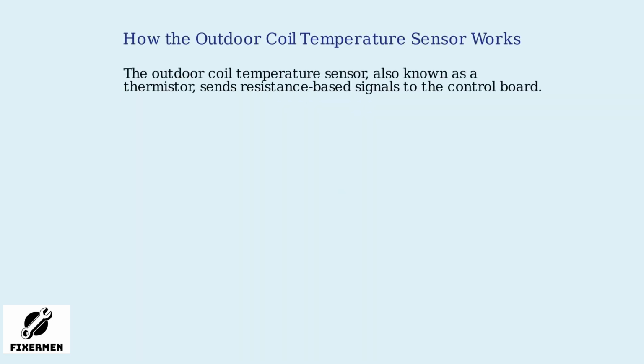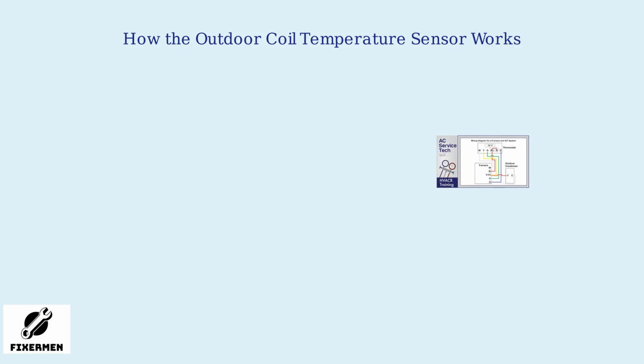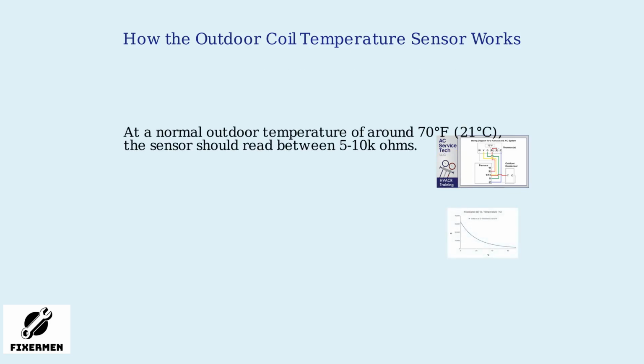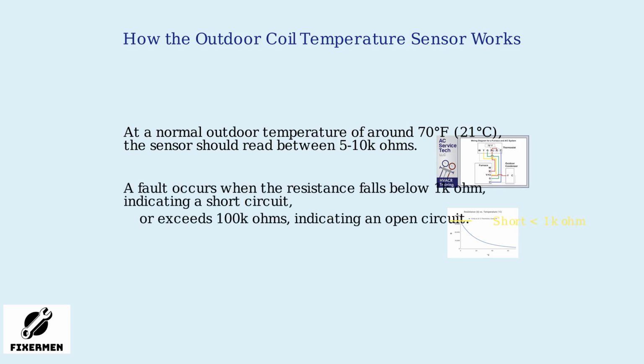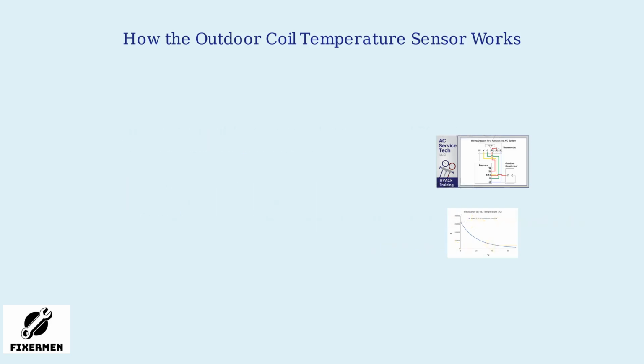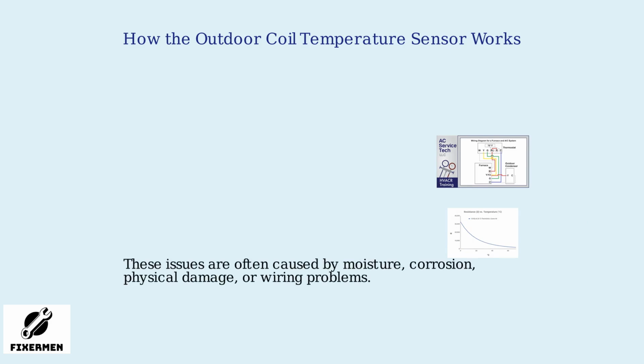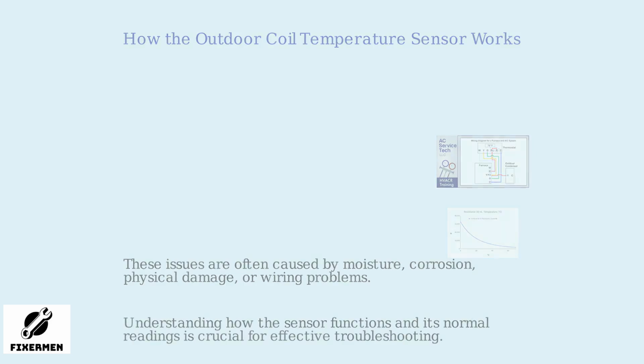The outdoor coil temperature sensor, also known as a thermistor, sends resistance-based signals to the control board. At a normal outdoor temperature of around 70 degrees Fahrenheit or 21 degrees Celsius, the sensor should read between 5 and 10 kiloohms. A fault occurs when the resistance falls below 1 kiloohm, indicating a short circuit, or exceeds 100 kiloohms, indicating an open circuit. These issues are often caused by moisture, corrosion, physical damage, or wiring problems. Understanding how the sensor functions and its normal readings is crucial for effective troubleshooting.